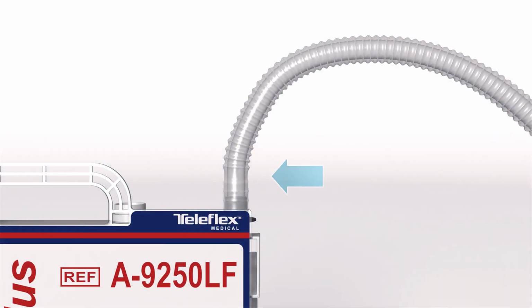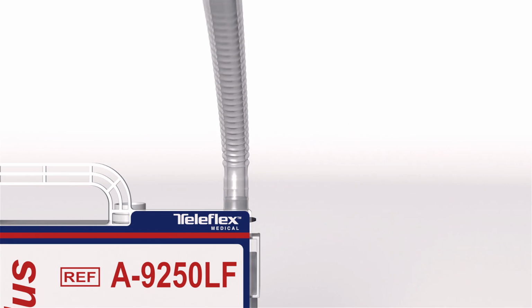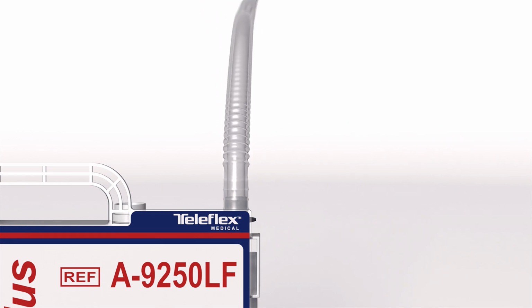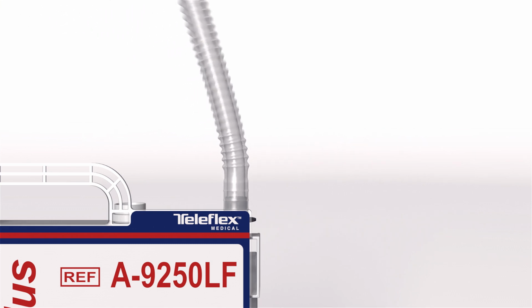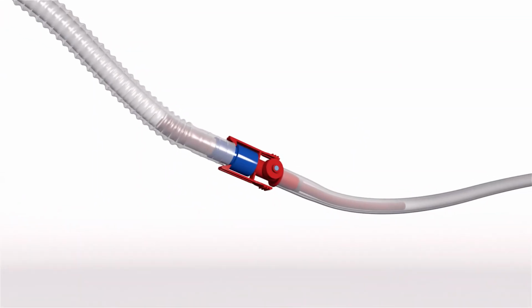At the junction where the 6-foot patient tube connects to the collection chamber, anti-kink tubing is incorporated to eliminate any unnecessary metal springs or other materials being in the critical blood flow pathway. Just beyond the anti-kink tubing is a pair of red and blue locking connectors, which allow for quick disconnection and reconnection to a new chest drainage unit when necessary. A needleless sampling port is located at the junction, allowing specimens of patient drainage to be taken whenever needed. Use only a standard Luer lock syringe to withdraw samples from the autotransfusion connector.